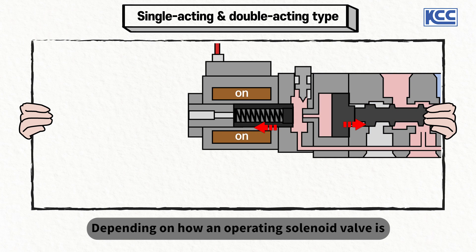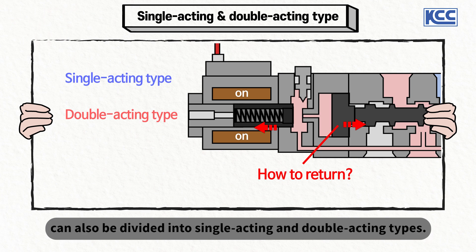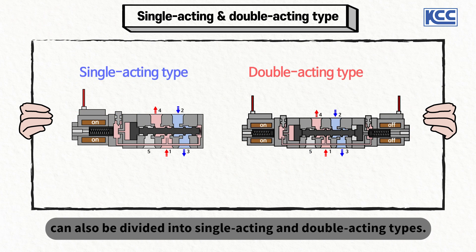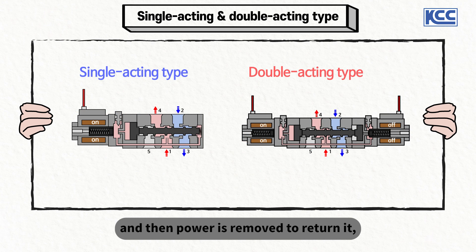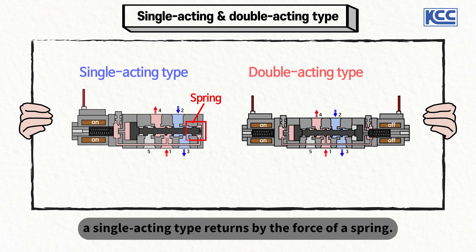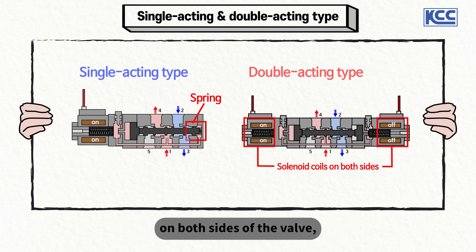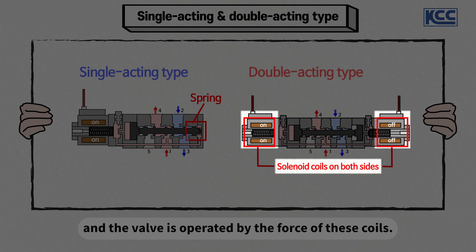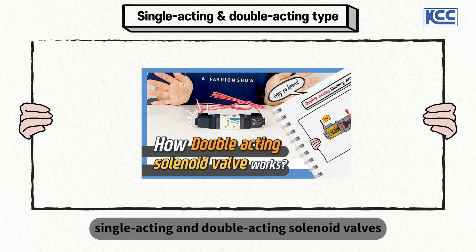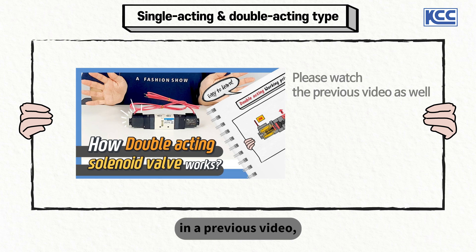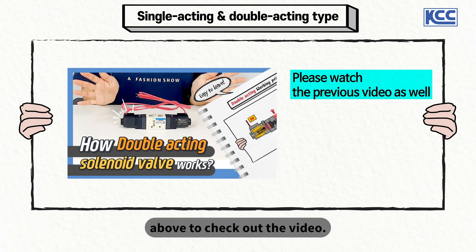Depending on how an operating solenoid valve is returned to its original state, solenoid valves can also be divided into single acting and double acting types. When power is applied to operate a solenoid valve and then removed to return it, a single acting type returns by the force of a spring. A double acting solenoid valve has coils on both sides of the valve and is operated by the force of these coils. Detailed characteristics were covered in a previous video — click the card above to check it out.